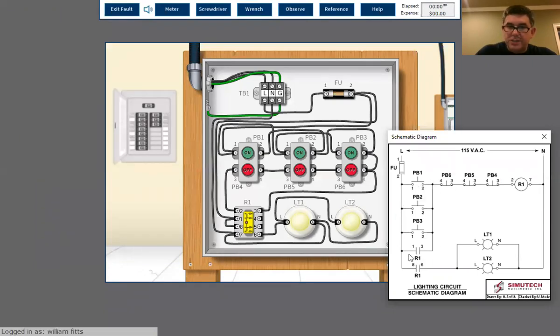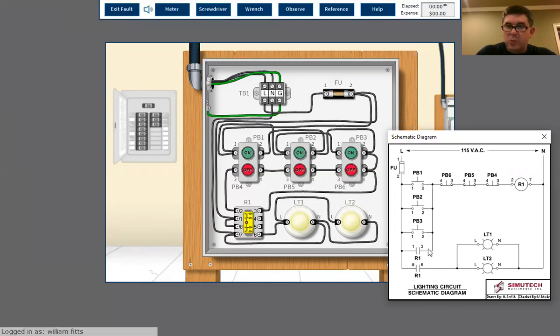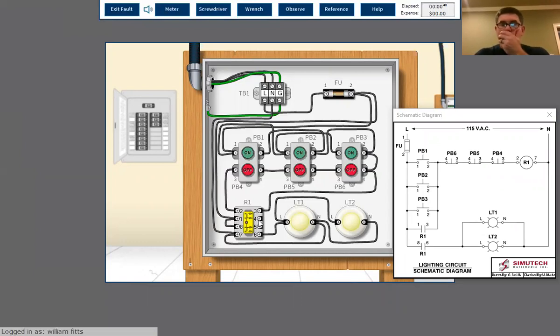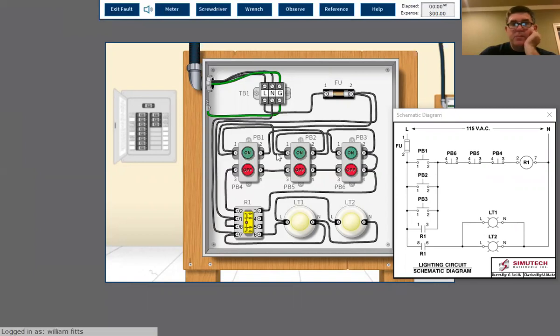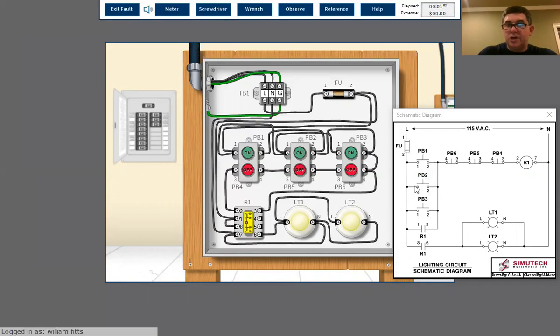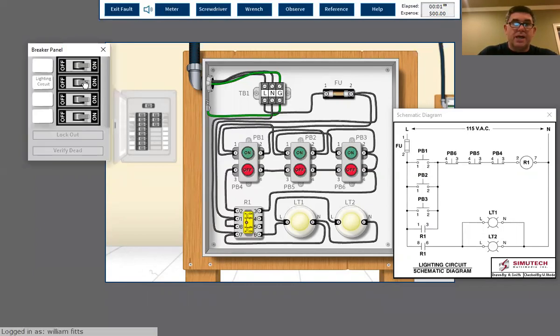I can turn it off with my stops, that means I've got - I feel like I have a short across this section of my circuit. It could be PB1, PB2, PB3, or R1 contact 1-3. One of those is holding in and it'll only turn off when you hit the off button. You can see my coil is lit up. So to me the easiest way - if you check power, you're gonna have power across them all. If you got one shorted and it's not working at all, there's no use in checking power. So we're gonna go ahead and just lock it out.